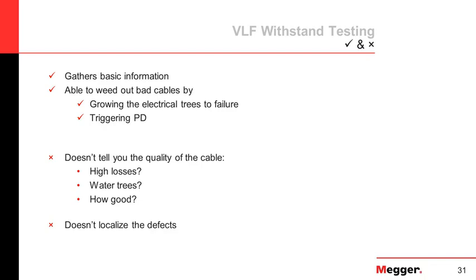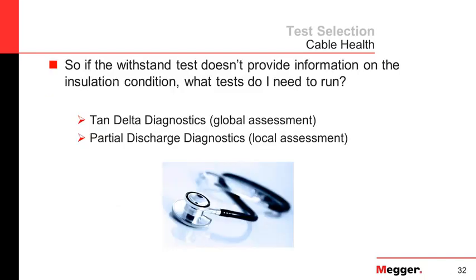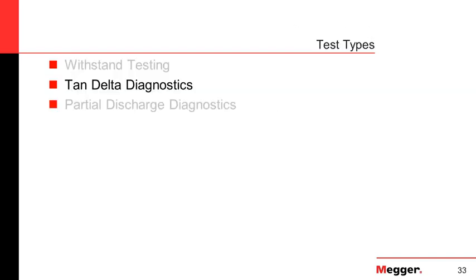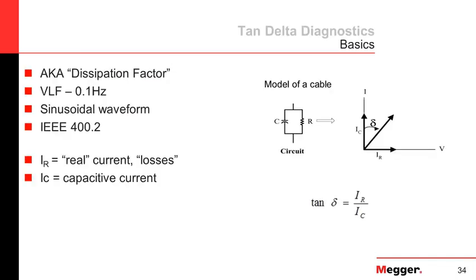If the withstand test doesn't provide a lot of information on cable insulation quality, there are two more diagnostics: tan-delta diagnostic and partial discharge diagnostic. Tan-delta, also known as dissipation factor, uses a frequency of 0.1 hertz in a sinusoidal waveform. Guidelines can be found in IEEE 400.2. It looks at the ratio of two currents — the real or resistive current and the capacitive current.